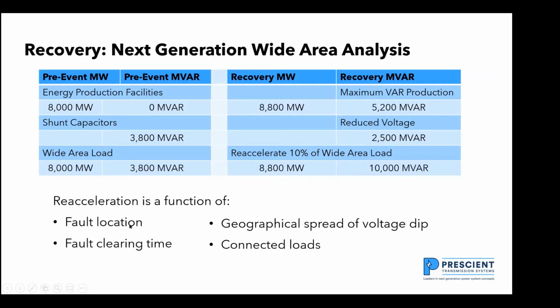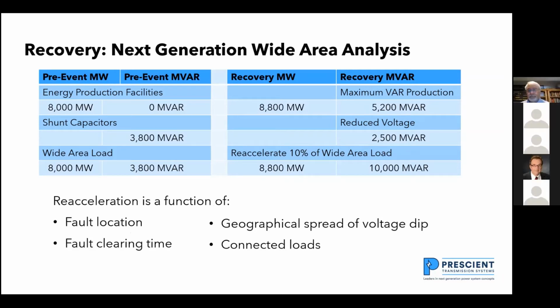So reacceleration is a function of the fault location. If I have a fault in a major city, like downtown Philadelphia, I'm going to shed load in Philadelphia, and I'm not going to get a large inrush for recovery. If the fault isn't in Philadelphia, though, let's say it's in Allentown, Pennsylvania, a three-phase fault there will be seen in Philadelphia, and that's the type of thing that's causing the recovery transient.